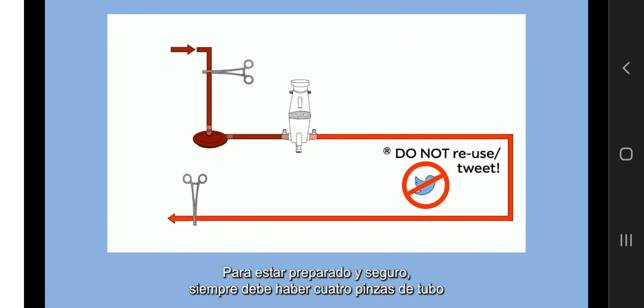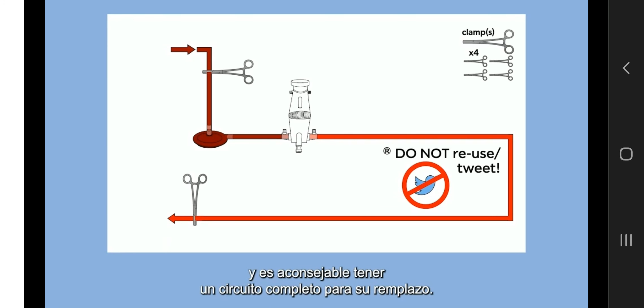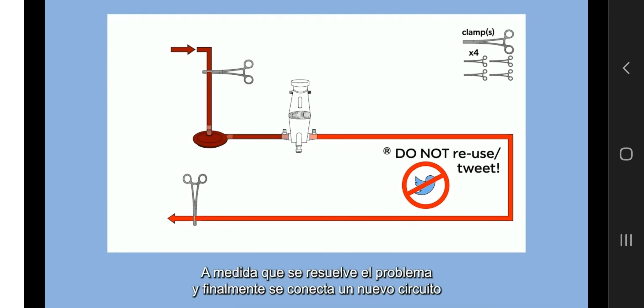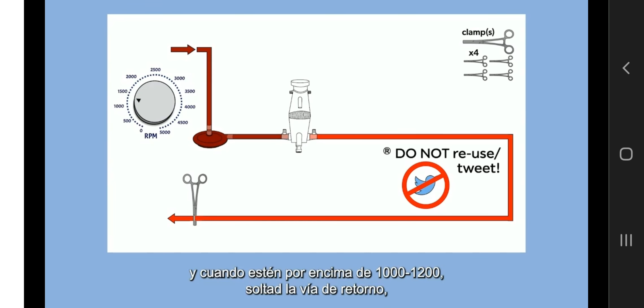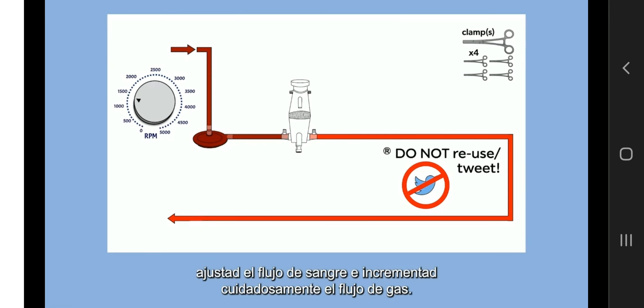To be prepared and safe, having 4 tubing clamps always available on the ECMO cart, 2 for clamping the drainage and return tubings, 2 to isolate any component or the whole circuit for replacement is advisable. As the issue is solved and eventually as a new circuit is connected, unclamp the drainage line, resume RPM, and when above 1000, 1200, unclamp the return line. Adjust blood flow and carefully increase gas flow.